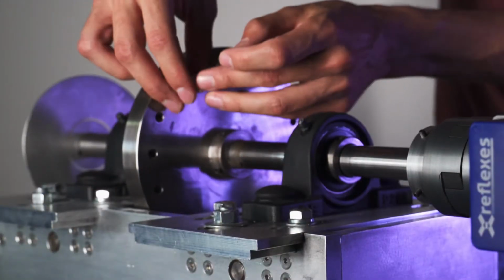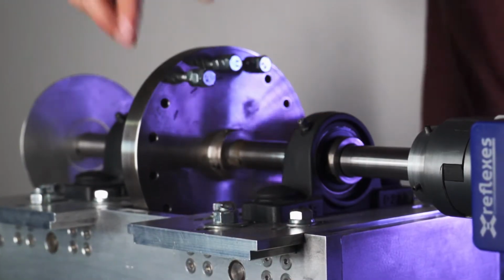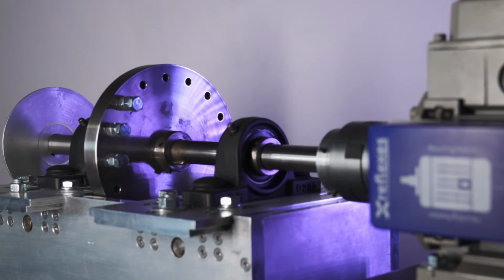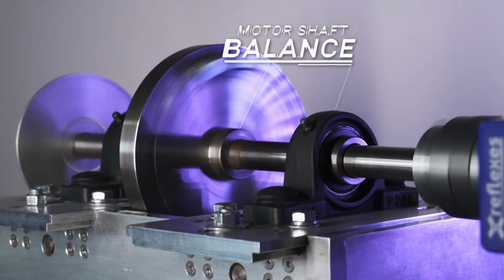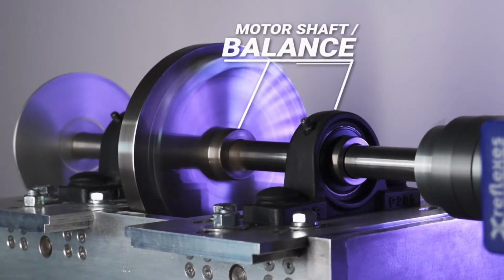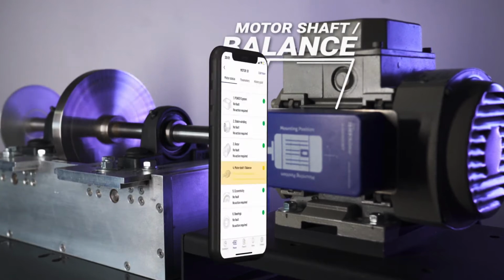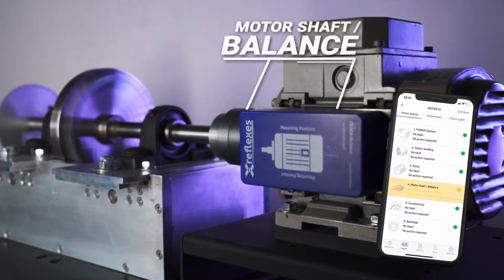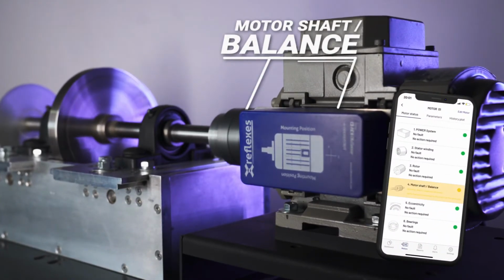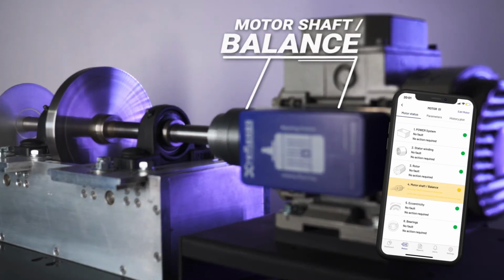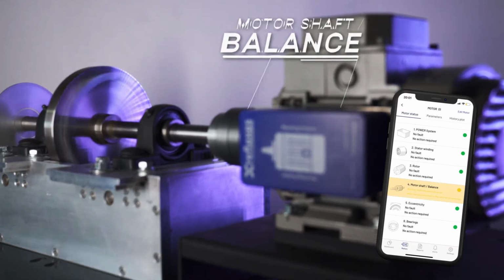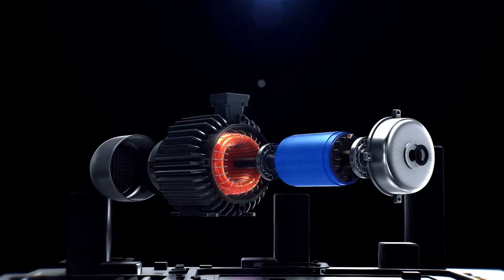Motor shaft balance. This mechanical problem is because of the fact that the rotor's center of gravity doesn't match with its center of rotation. This is caused by an unequal mass distribution. A lack of balance increases the motor power consumption and vibration levels, decreasing the bearing's useful life.